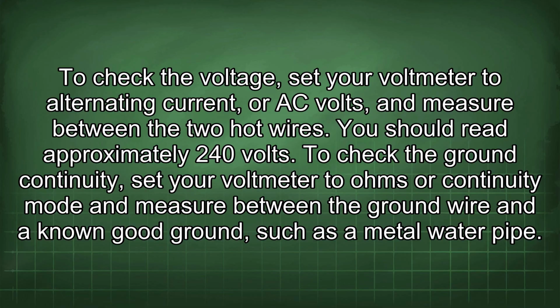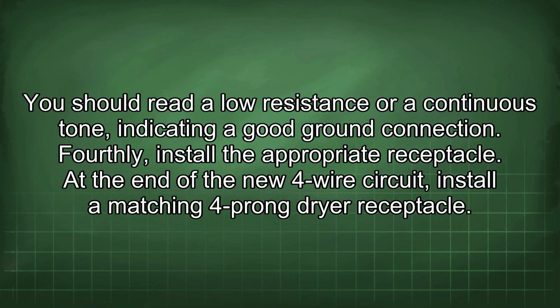To check the ground continuity, set your voltmeter to ohms or continuity mode and measure between the ground wire and a known good ground, such as a metal water pipe. You should read a low resistance or continuous tone indicating a good ground connection. Fourthly, install the appropriate receptacle. At the end of the new 4-wire circuit, install a matching 4-prong dryer receptacle.